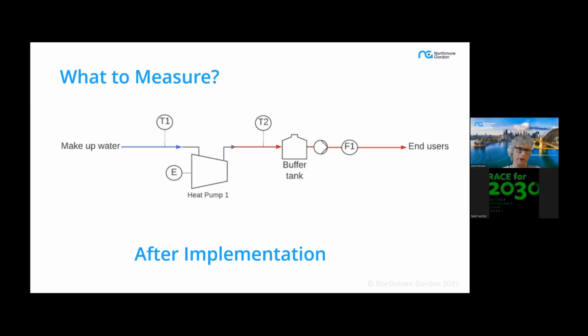The reason the flow meter there is after the buffer tank is because the flow into the buffer tank won't provide a direct measure of the actual energy consumption or heat demand profile of the end users. It will smooth that out. So it's important to have that flow meter after the buffer tank.